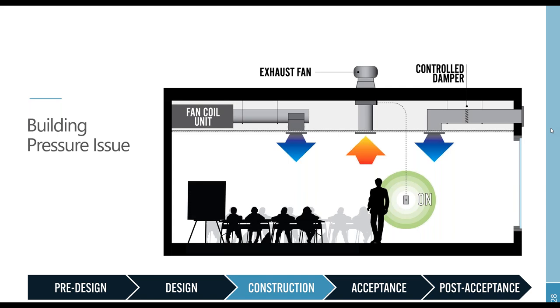We turned the exhaust fan on, we checked, and there was air coming in through the damper. So all was good. However, we then turned the fan back off. And in this instance, we noticed that air was now leaving the room through this area. So this damper was supposed to close automatically when the exhaust fan was not on.